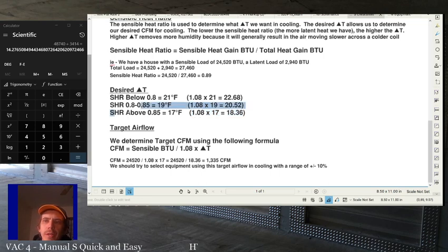Sensible heat ratio of 0.8 to 0.85 is a 19 degree delta T. So this is kind of average. This is pretty close. So we usually want a 20 degree delta, right? 20 degree delta is what we always say we want on a split on an air conditioner, which is wrong. We don't always want a 20 degree delta. But that's pretty close, right? And look, that's pretty close because our sensible heat ratio is usually somewhere between 0.8 and 0.85. We're right in that range. So if we're in this range, a 19 to 21 degree delta T, a 20 degree delta T usually does a pretty good job of handling humidity and sensible load.